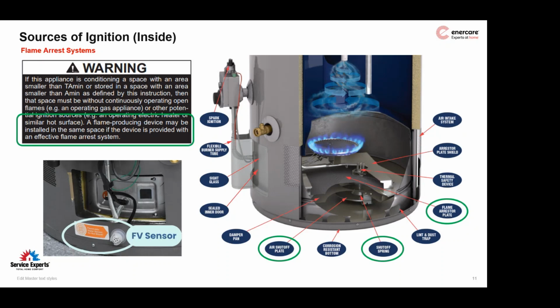Right now, the current understanding is that as long as the room that spark generating appliance is in, if it's the dryer or the electric, maybe a fireplace, as long as we meet that TA minimum room size for the mechanical room, if the door, for whatever reason, the mechanical room happens to be sealed up with one of these spark generating devices, that's enough space to allow for that piece of equipment to be there. That is our current understanding, but we are still learning, and we're still trying to get clarification from Lennox, because their manual is probably the most strict sounding, especially in this warning.